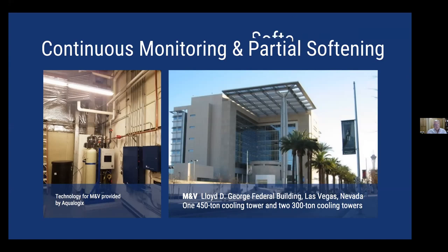Anyway, if you look at the picture on the left, this is the technology installed at the site. As you can see, it's a very small skid that sits in the corner of the room. It's got a little brine tank to the left of it, but it doesn't take up a lot of space. That skid basically dropped in and tied into the water piping, and there's also drain piping. So when it comes to installation, it makes sense to put it close to the cooling water supply piping and to a drain, because a lot of the installation cost is the piping cost.